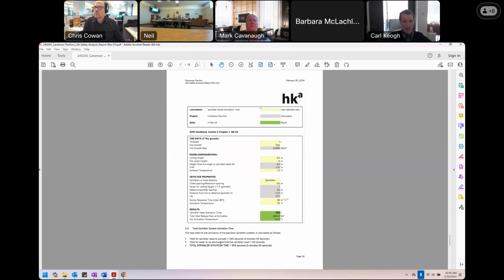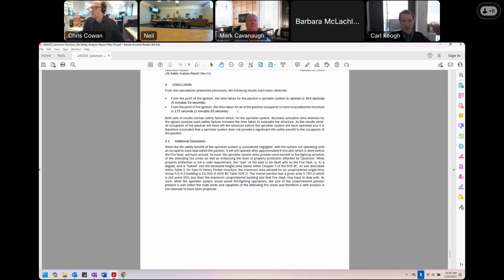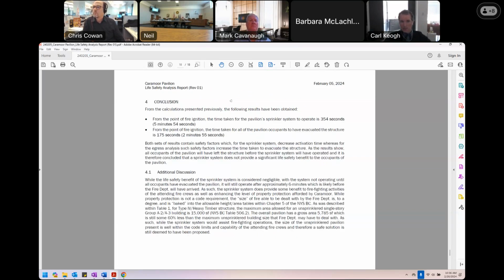If we now compare that, on page 17 we have our conclusion here, which is that from the point of fire ignition to the sprinkler system operating is just short of 6 minutes. However, we're comparing that to an evacuation of the structure at just under 3 minutes, even with some factors of safety included. So we can see we've got a decent margin of safety between what we've estimated it would take to get out of the pavilion versus the time it would take to activate the sprinkler system and discharge water onto any fire.